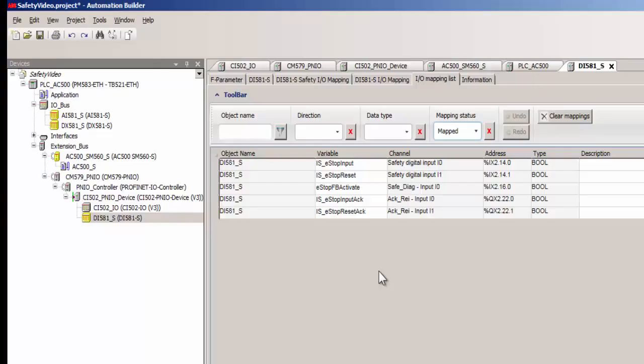Similarly a single channel type reset button is wired to the channel 1. Appropriate acknowledge reintegration bits are mapped, so that the channels could be reintegrated should there be a channel passivation. After the cause of passivation is removed and a reintegration action is initiated either manually or programmatically.